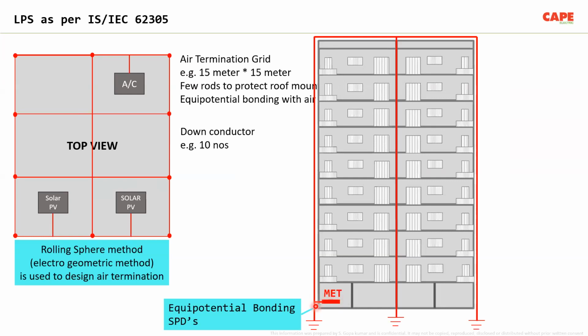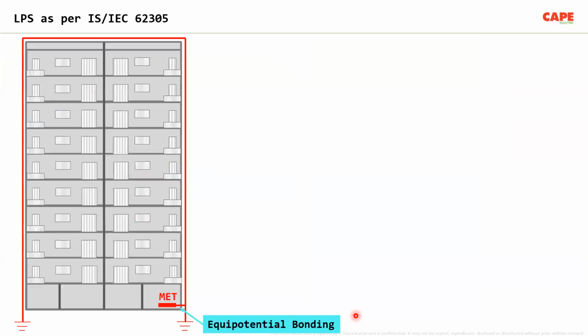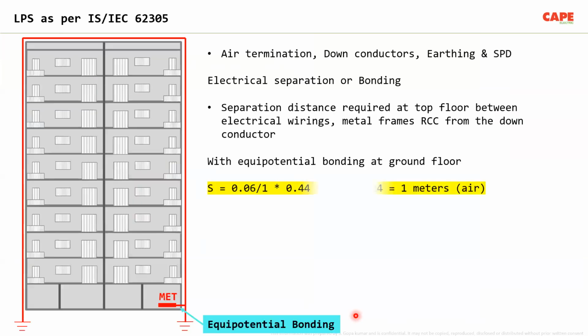This is very important. Of course, in most of our installations in India, this does not exist and people don't allow you to connect this way. Actually, this is very much mandatory. And as an option, you can also go for a type B earth electrode. So basically, it consists of lightning protection, a mesh at the top, several down conductors, a ring earthing or individual earthings, plus an equipotential bonding to the MET. So this is how it is made.